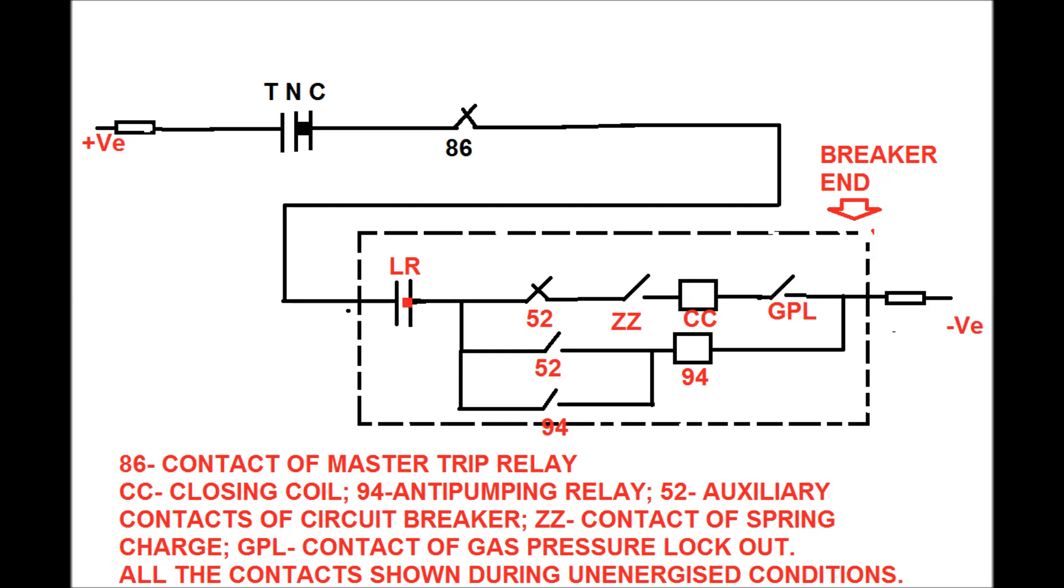52 is the auxiliary contact of circuit breaker. ZZ is the spring charge contact. Whenever spring is in charge condition ZZ remain in close position and CC is the closing coil.